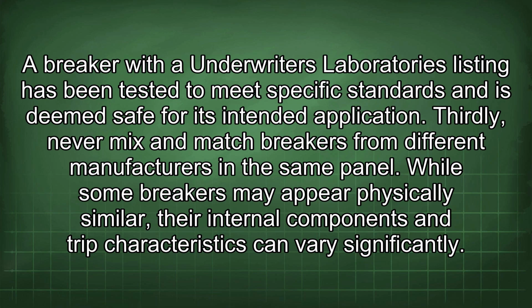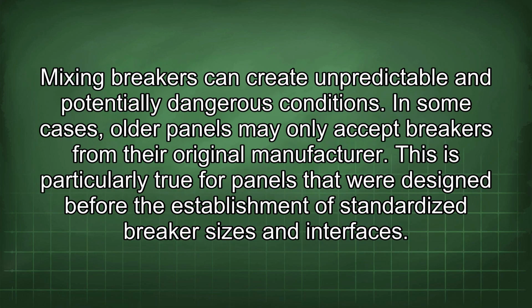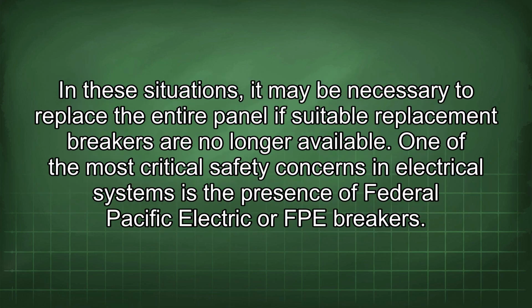While some breakers may appear physically similar, their internal components and trip characteristics can vary significantly. Mixing breakers can create unpredictable and potentially dangerous conditions. In some cases, older panels may only accept breakers from their original manufacturer. This is particularly true for panels that were designed before the establishment of standardized breaker sizes and interfaces. In these situations, it may be necessary to replace the entire panel if suitable replacement breakers are no longer available.